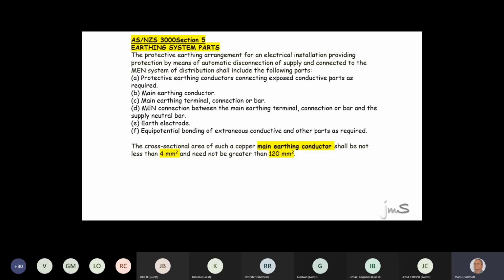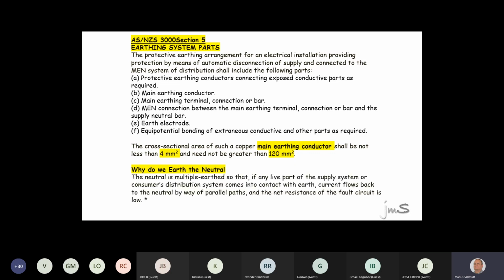Right, guys? That's enough for you on switchboards. But wait, there's a little bit more. Why do we earth the neutral? Why do we put a link in the first one? Gentlemen and ladies, if you don't, you could have current flow through the earth back if there was an earth fault. In other words, there's no link. Also, you do not guarantee a parallel path if there's a fault. Number three, the current, because of the fault, might be so low that it will not blow or trip the breaker. And if you don't link it, you might have a potential voltage between neutral and earth. That's why, if mommy touched the sink, she might get a bit of a shocking experience. All right? Be careful. That's just nice to know stuff.